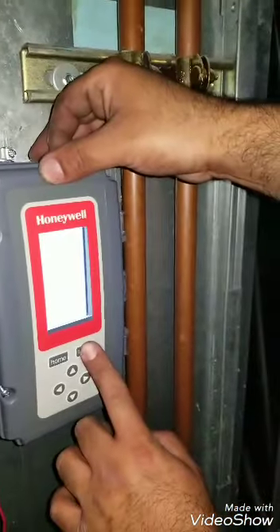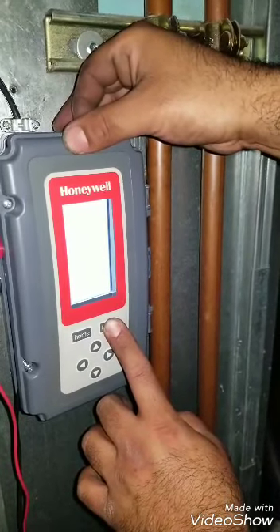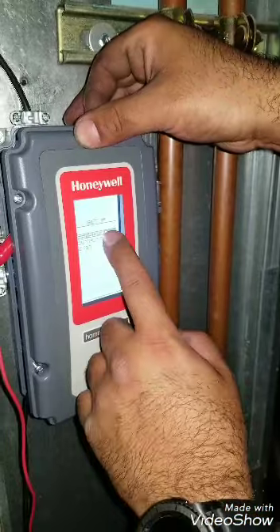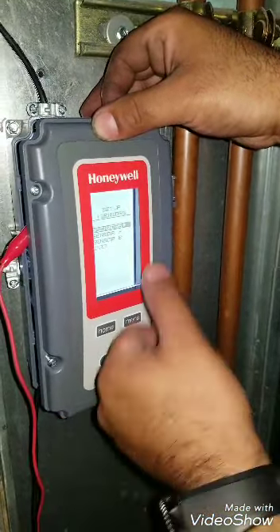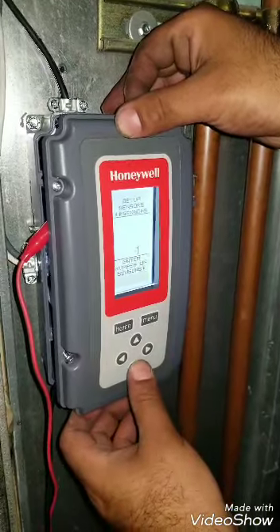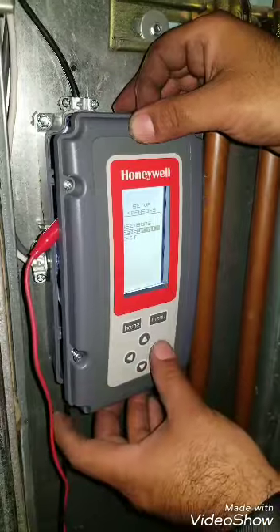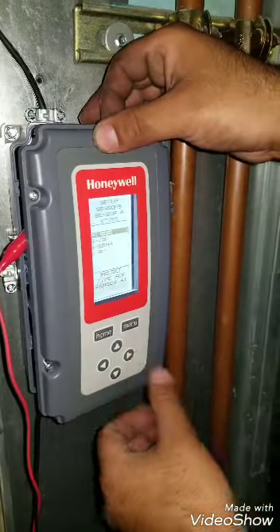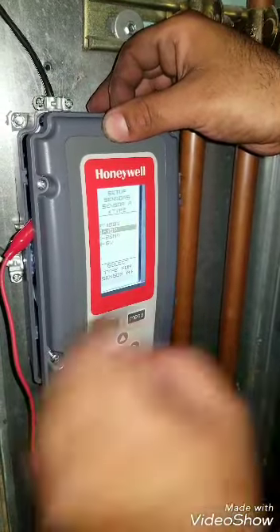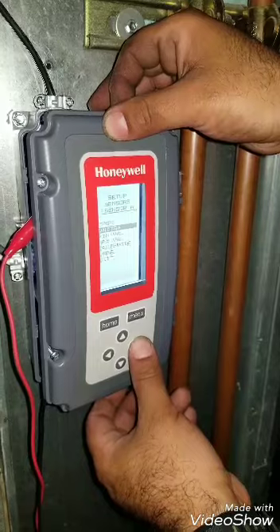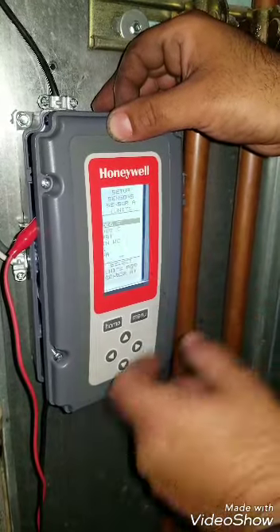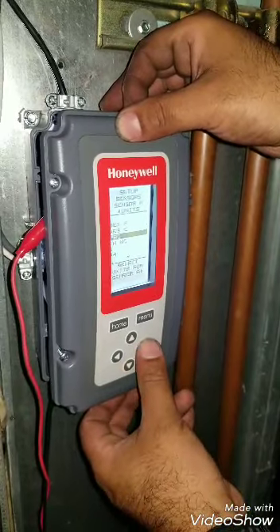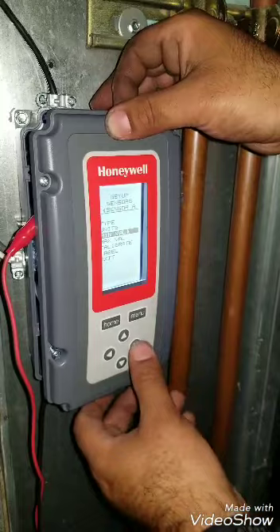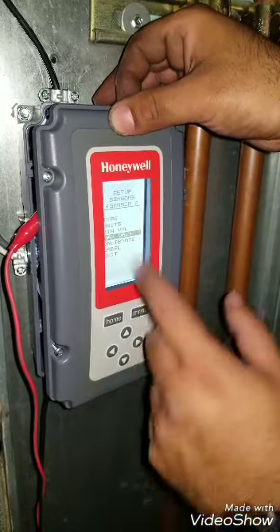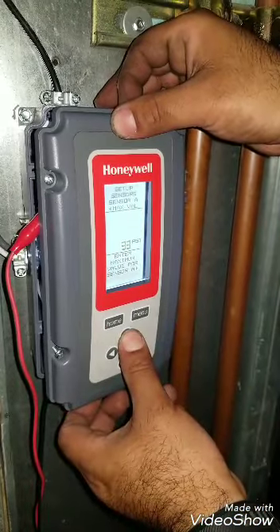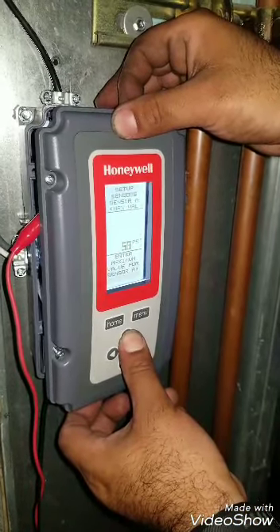All right, you hold the menu button for a couple seconds. You're gonna get set up. You're gonna go to sensors. You're gonna hit the right arrow and write number of sensors, 1. Sensor A. Type, it's going to be 0 to 10 VDC. That's your transducer coming in. And then set up degrees Fahrenheit. You want PSI, right? And then minimum value is going to be 0 PSI. And the maximum value is going to be 500 PSI. That's what the transducer is, 0 to 500 PSI.